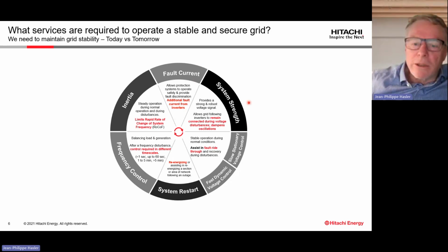Then we have to increase the grid strength, of course. And another main task is to improve the voltage control of the grid, because we have to improve the voltage control not only for the steady state, but also for transient behavior. And that is what is also called fast dynamic voltage control. That means if we have an oscillation caused by subsynchronous resonance, it's very important that we provide the proper damping. A system restart, of course, is very important.